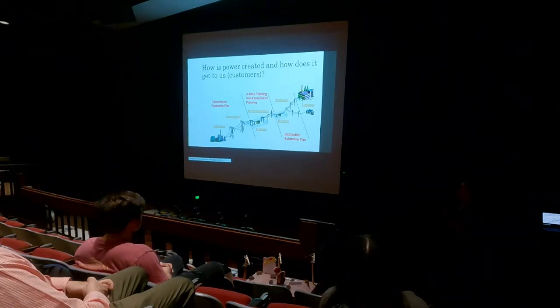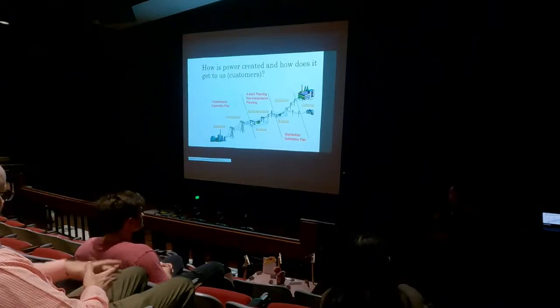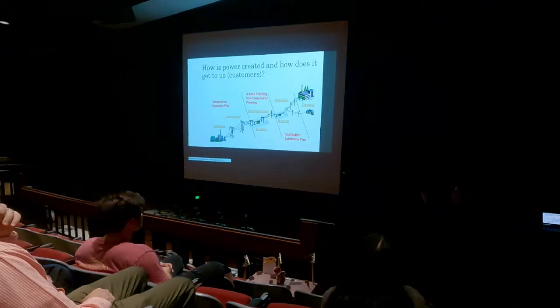So that's where I work. Transmission is high voltage lines. After it goes through those towers, maybe an H-frame or so, it gets to subtrans. Subtrans is your typical substation, where electricity is lowered. So we might go from 500 kV to 66 kV, and then there's another substation where it's converted to distribution. Distribution is typically 12 kV, 16 kV. After it gets to distribution, you've probably seen those power poles near streets, those are usually distribution, 16 kV or 12 kV. It's then transported to your home where you can use it for all those different things.